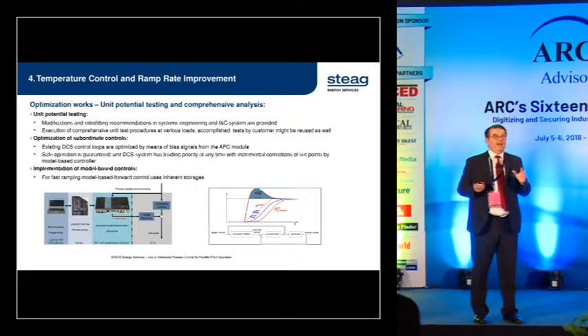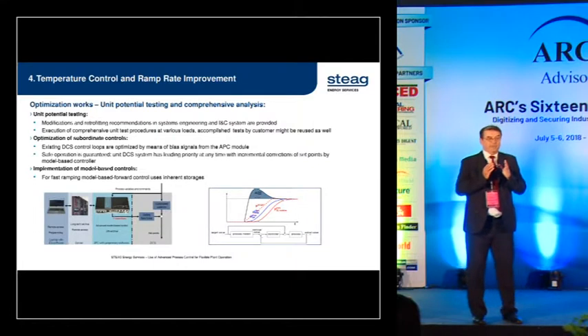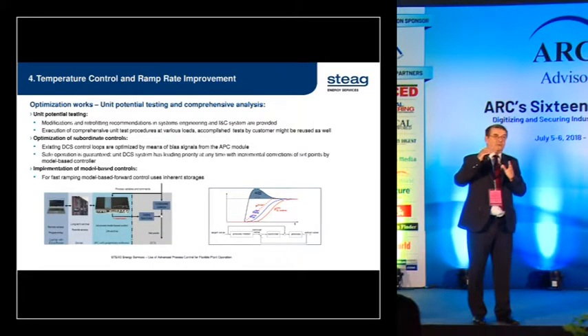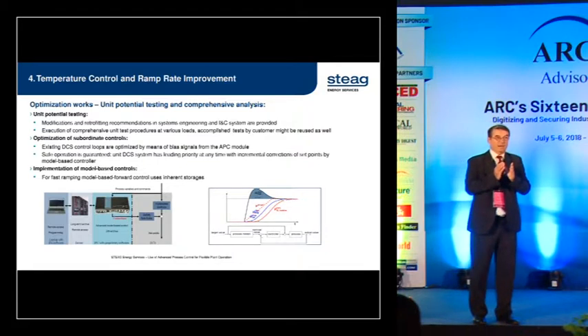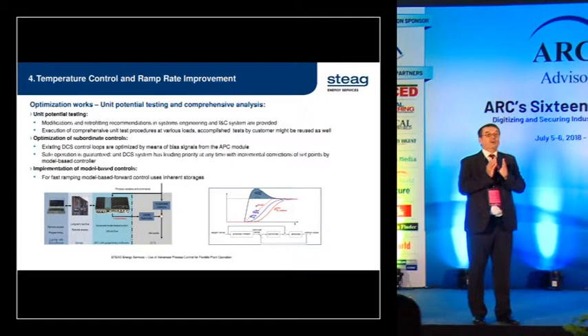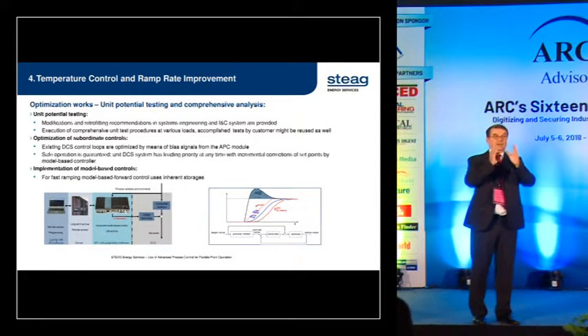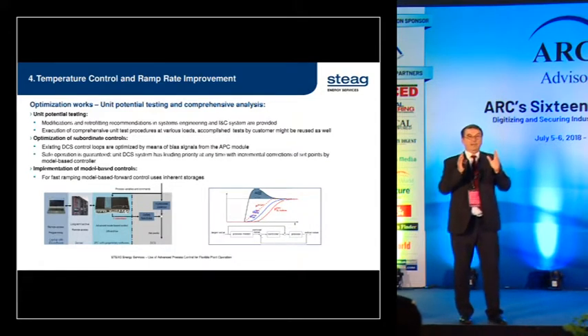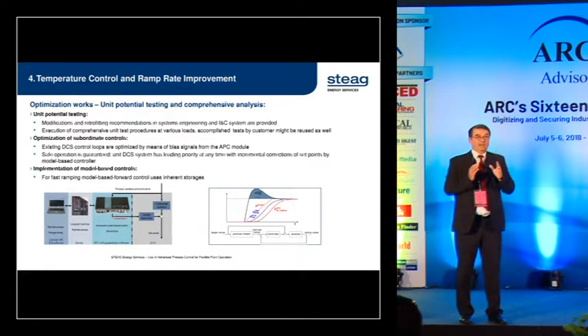this software, we have the model which predicts temperature differences in the highly loaded component. The fast ramping of the operation causes high temperature differences in the thick wall components. And these high temperature differences cause higher fatigue. And one of the methods, of course, is to put constant limits and say that if the temperature difference increases by factor X, then the firing rate will be slowed down.